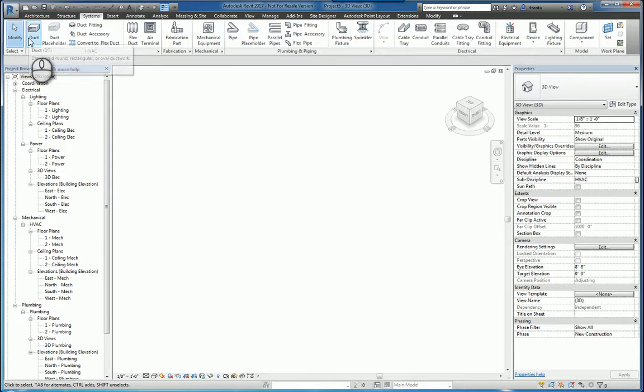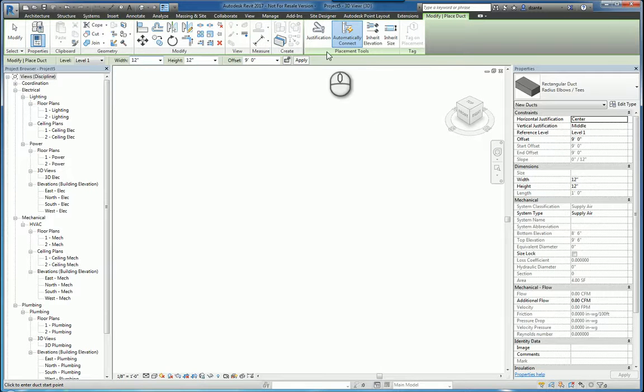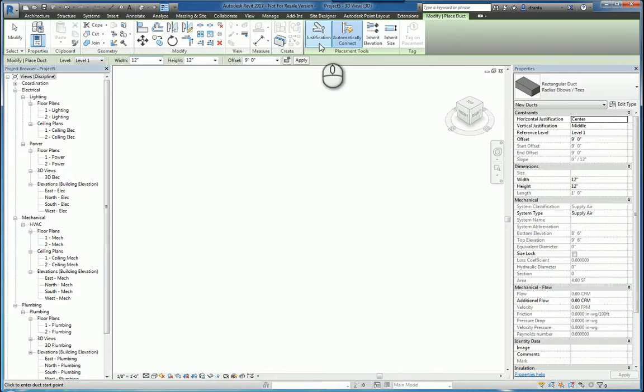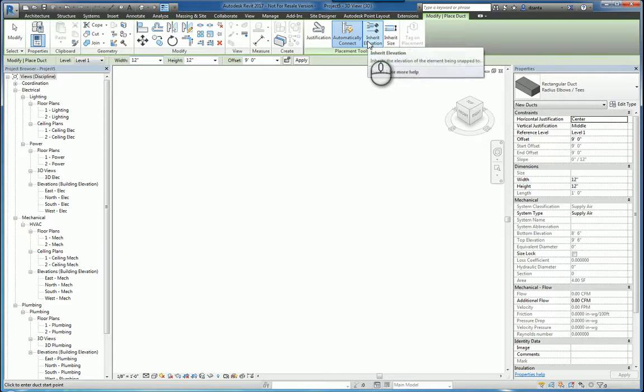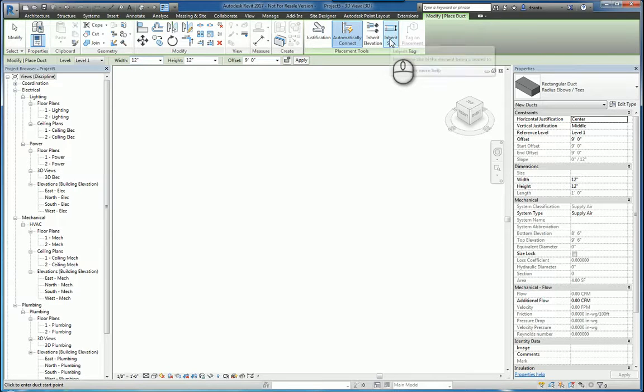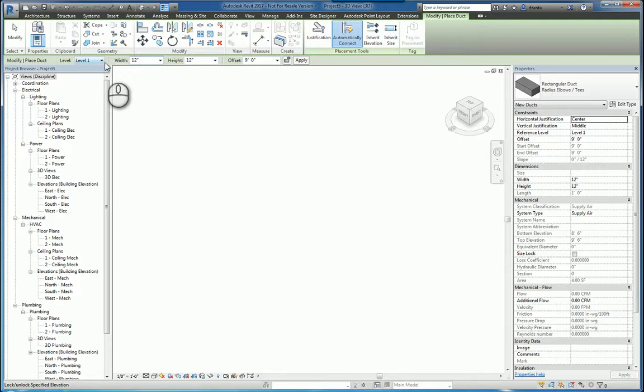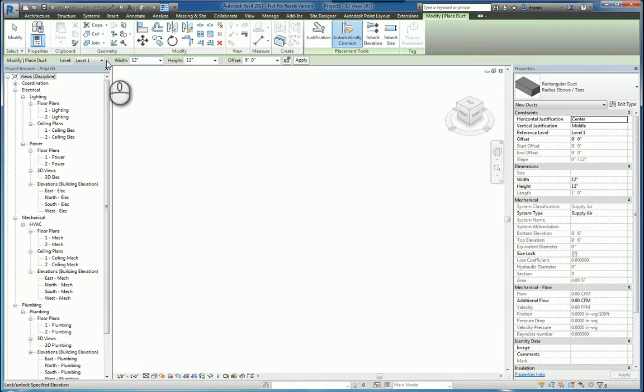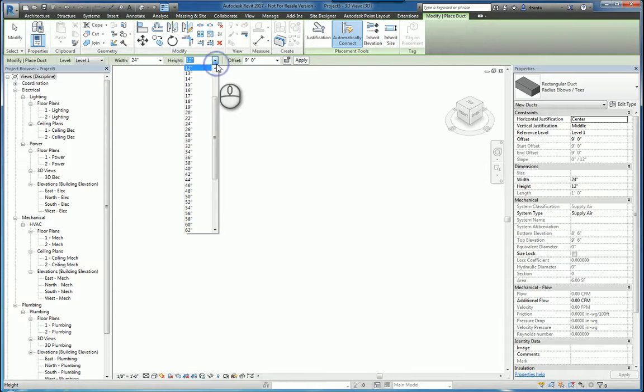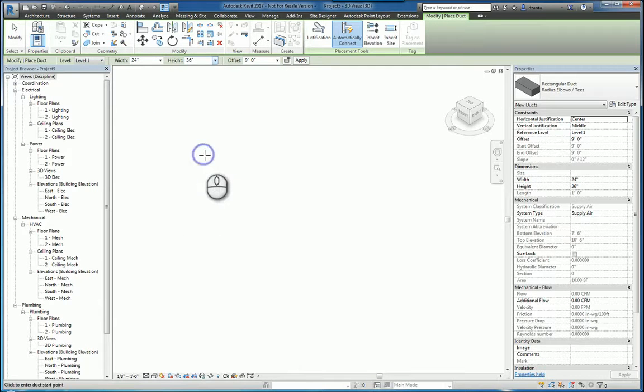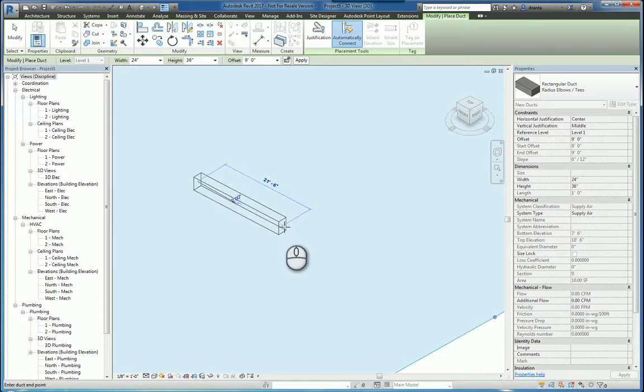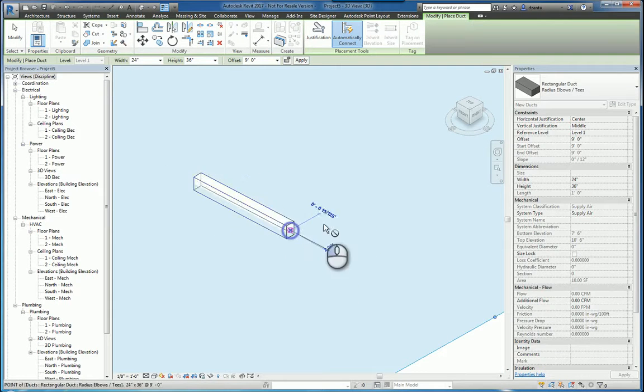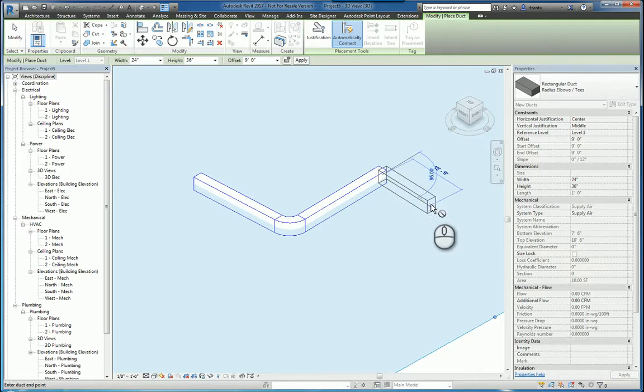Let's go ahead and delete this. We'll start with the duct command. When you start with the duct command, in the placement tools there are several features: justification, automatically connect, inherit elevation, and inherit size. You also have the options toolbar for specifying the descriptive information about what you're about to place. For example, I'm going to go ahead and put in a ductwork that's 24 inches wide by 36 inches high at 9 feet. And I'll zoom out a little bit, and then I'll place it. And as I'm drawing it, it just draws it without a problem.